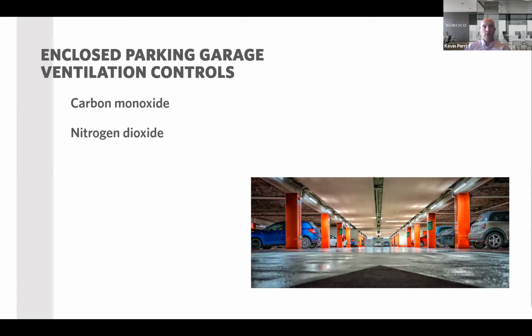Okay, parking garages. They do have mechanical systems in there. With those mechanical systems, what we're used to is ventilation. Right now, it's just carbon monoxide detectors that trigger our exhaust fans to come on. In the 2021 code cycle, they're saying that enclosed parking garages need to have carbon monoxide detectors in conjunction with nitrogen dioxide detectors. Those two things are what's going to trigger the exhaust systems to come on in enclosed parking garages.